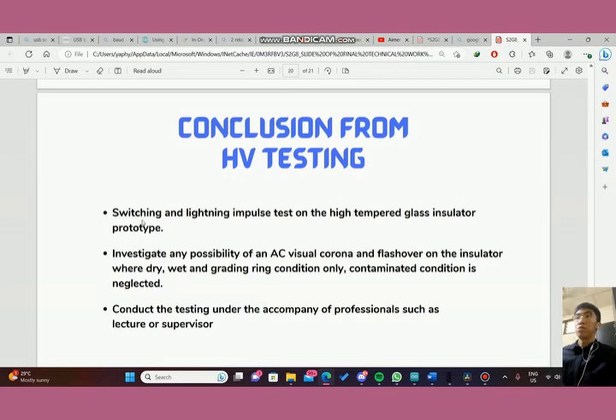This method is a destructive testing method, so a couple of pairs of insulator prototypes need to be prepared to conduct the experiment and to collect further data results. According to our component selection, the switching and lightning impulse tests are performed on the insulators to investigate any possible AC corona and flashover on the insulator under dry, wet and grading ring condition only. So contamination is neglected.